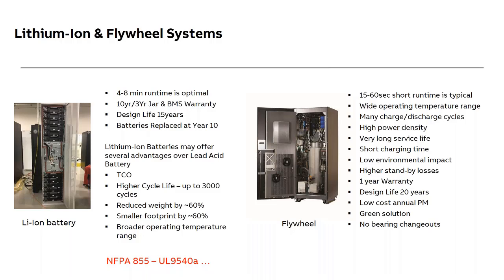There's a way around that, and the entire business is working on getting a UL listing, what's called a UL 9540A listing. We have that for the batteries we are using, and basically the battery manufacturer has to prove that a fault in one battery will not propagate to other batteries. That's the fear, and that was the reason for the 855.